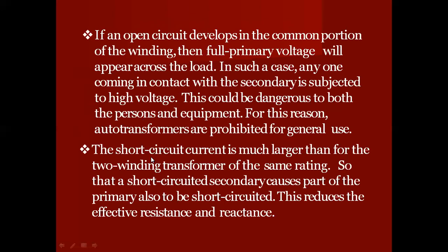The short circuit current is much larger than for a two-winding transformer of the same rating. So a short-circuited secondary causes part of the primary also to be short circuited. This reduces the effective resistance and reactance.